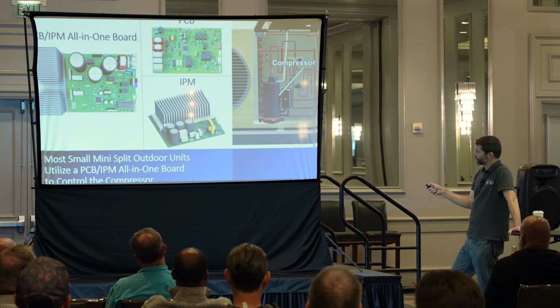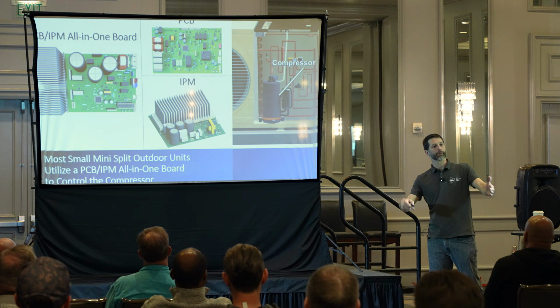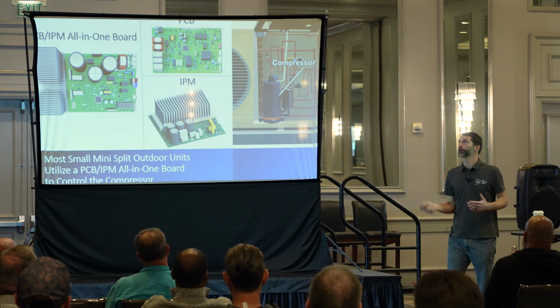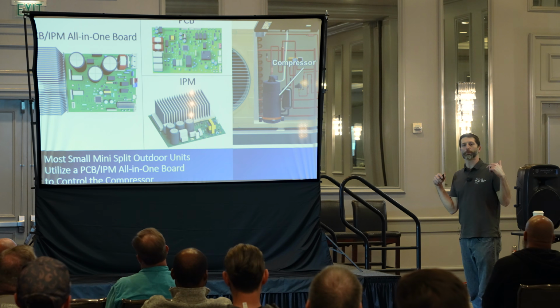They hook the low-pressure line that's going into the accumulator, putting a block heat sink touching the tube, so you're absorbing the heat from the IPM module right into the refrigerant. Because if somebody forgets to do the maintenance on their system, it's not going to destroy the circuit board and give the equipment manufacturer a bad name.